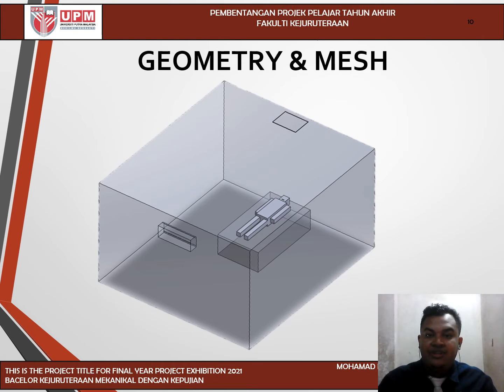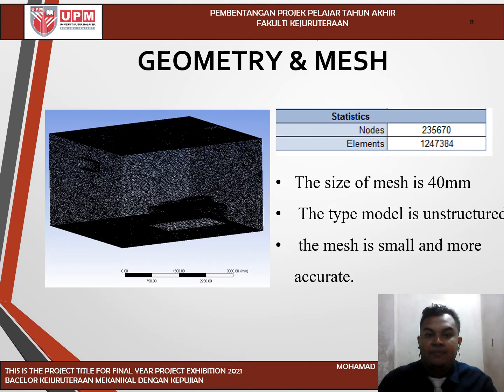This figure shows the 3D isolation room modeled in SOLIDWORKS. The geometry model room dimensions are 4 meters in length, 4.5 meters wide, and 2.5 meters high, with a volume of 45 cubic meters. The isolation room model consists of one split unit air conditioner, one inlet supply vent, one exhaust grill wall, and one patient complete with a hospital bed. The mesh was done using the ANSYS meshing software. The model type is unstructured, with an element count of 1,247,384 and 235,670 nodes. The mesh size is 40 millimeters.